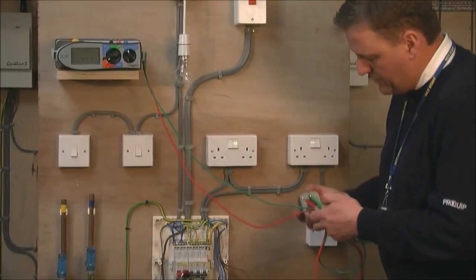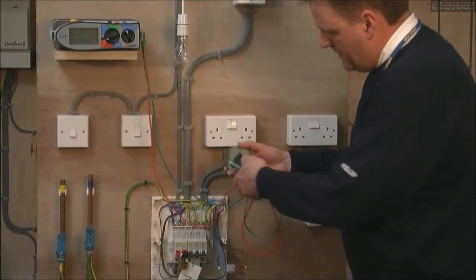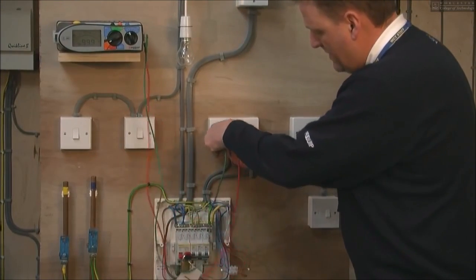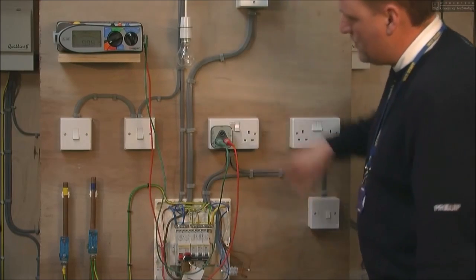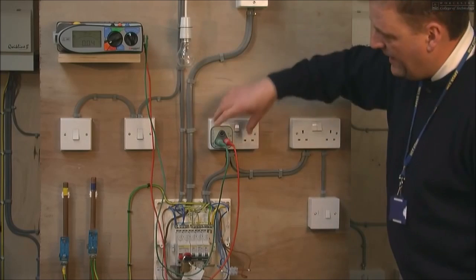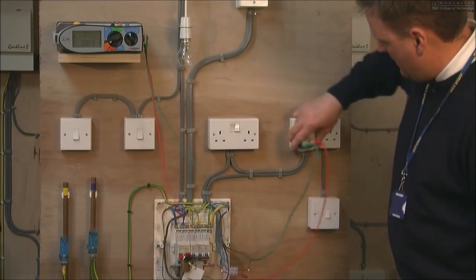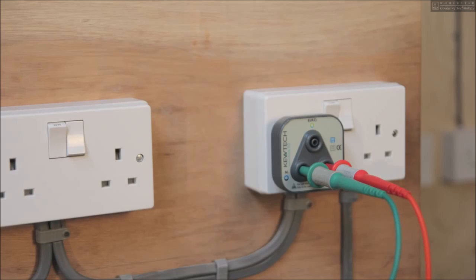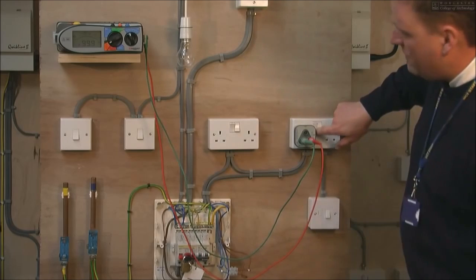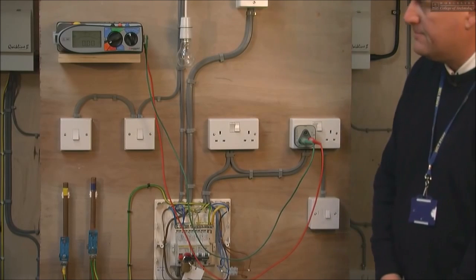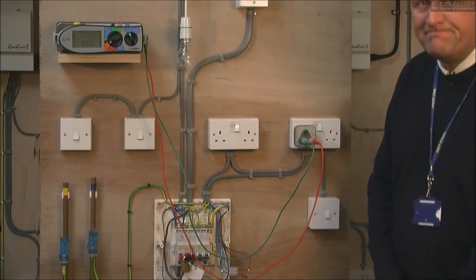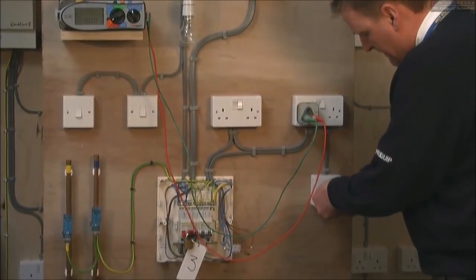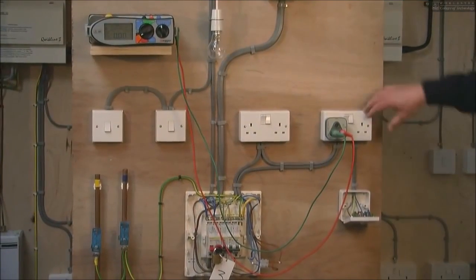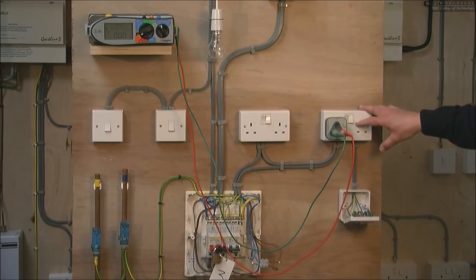Having connected the line and neutral together, we then go around each of our sockets. Remember to switch them on. And you should get a reading of the equivalent of little r1 plus little rn divided by 4 will give you the readings at each of the sockets. As you can see, this one, the socket switched off, you switch it on, and that brings our tester to close the circuit. All the readings in the ring should be the same, or very close.